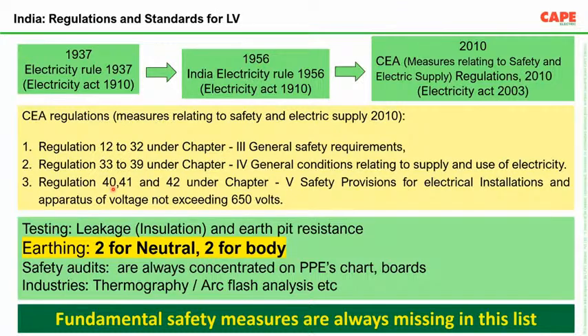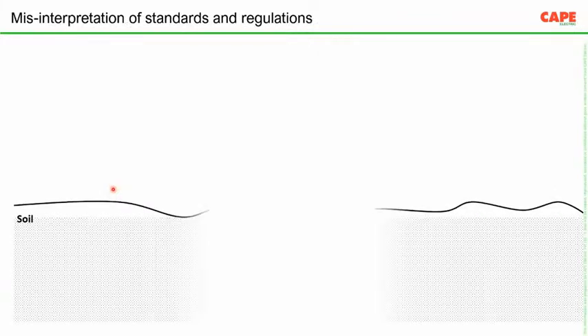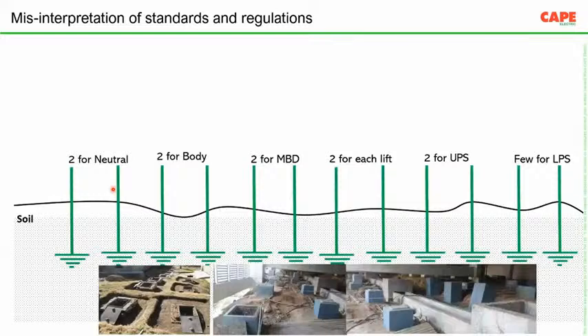So more than that, so far I have not seen any safety audit more than this, especially the leakage test, that means the insulation resistance test, the earth pit resistance test, PPEs, charts and boards, thermography and arc flash. More than that, the test which is mentioned in the IEC is mostly... I am yet to see a building in India which is tested as per the IEC 60364. I repeat, I am yet to see a building which is tested as per IEC 60364. This is very important because I am coming to the next slide.